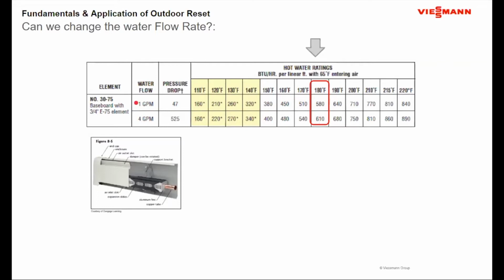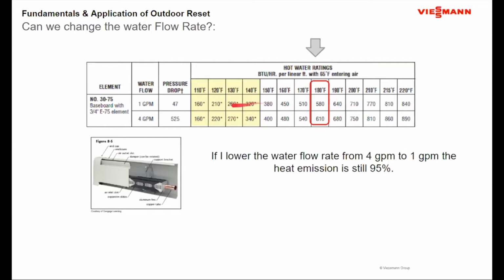So with baseboard, if I'm flowing at 4 gallons a minute, I'm getting about 600 BTUs per linear foot. If I drop that flow rate from 4 gallons per minute to 1 gallon per minute, I'm now down to 1/4 of the flow rate I originally had, or 25% of the flow. But if you look at the numbers here, I went from 610 BTUs per linear foot down to just 580. Okay, so I've reduced it to 1/4 of the original flow, but I'm still getting about 95% of the energy out of that heat emitter.